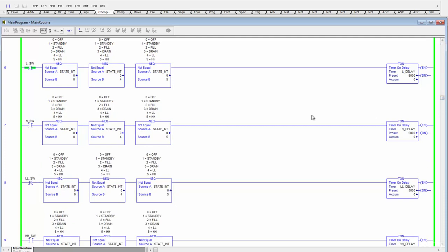So you've got all the information, but then just imagine if I've actually written this program the way I usually write a larger program. I have one ladder which has got my analog inputs. I have another ladder for analog outputs. I have another ladder for control. I have another ladder to manage the machine's state. I have another ladder which has my alarms. If I have a lot of alarms, I might break alarms down into analog alarms and digital alarms. So, I can have easily 10, 20, 30 ladders all working together in one single program.